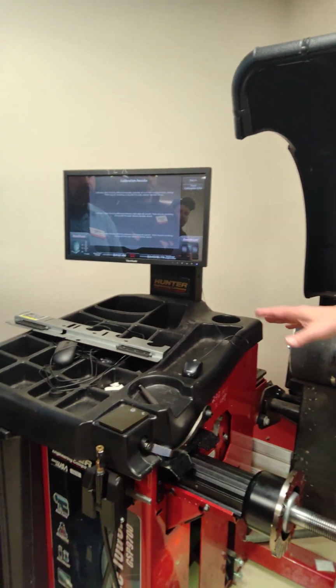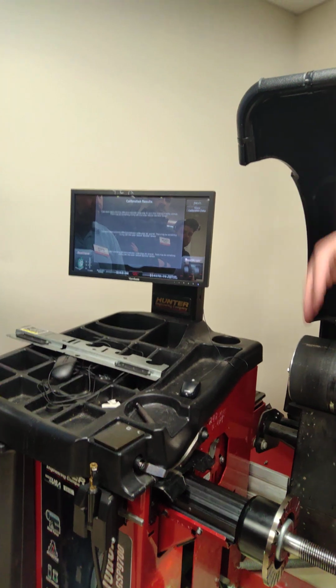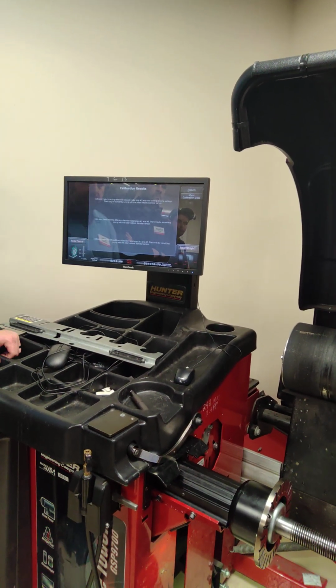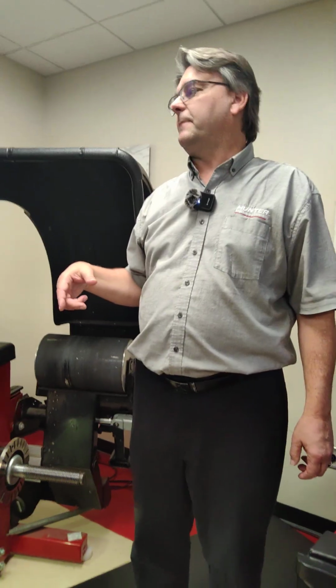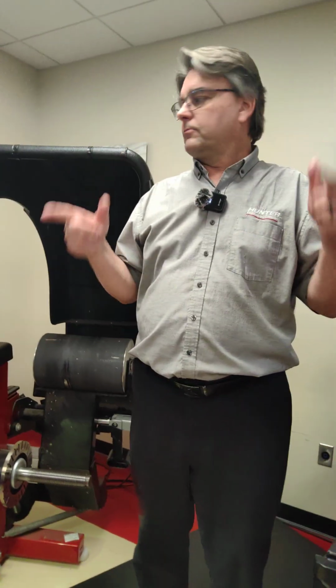And if you notice, you have 3 failed bits, so you have 3 failed steps, and you have 3 hints. The machine itself is basically trying to tell you, hey, I think something's wrong in this area here. You might want to concentrate all of your diagnostic prowess and abilities here instead of chasing after unicorn squirrels over here. That's cool. But again, you have to read it right to left. If it says passed, I think the air pressure one only has like 3 of the 16, but all the other steps have 16 out of 16 steps.